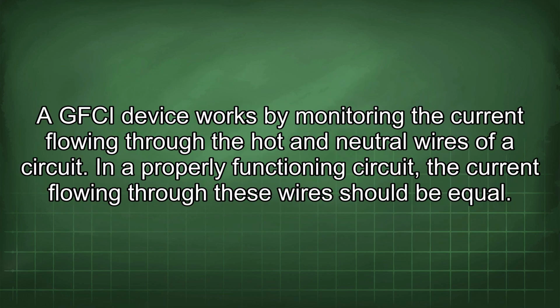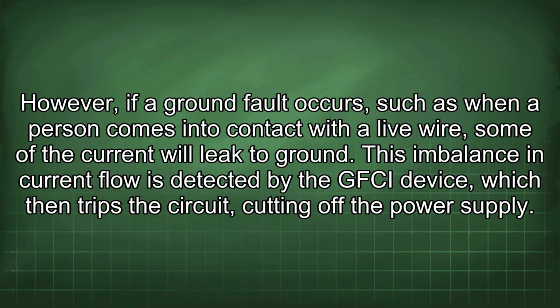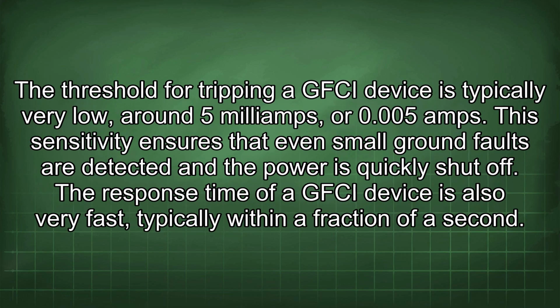A GFCI device works by monitoring the current flowing through the hot and neutral wires of a circuit. In a properly functioning circuit, the current flowing through these wires should be equal. However, if a ground fault occurs, such as when a person comes into contact with a live wire, some of the current will leak to ground. This imbalance in current flow is detected by the GFCI device, which then trips the circuit, cutting off the power supply. The threshold for tripping a GFCI device is typically very low, around 5 mA or 0.005 amps.